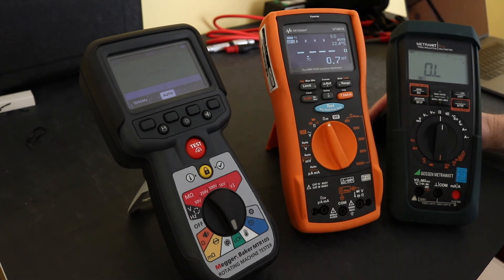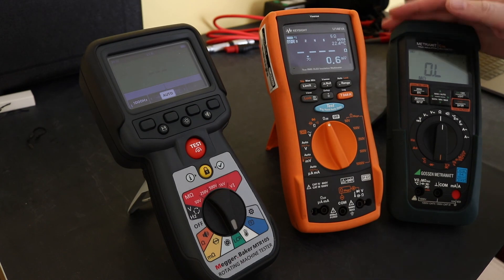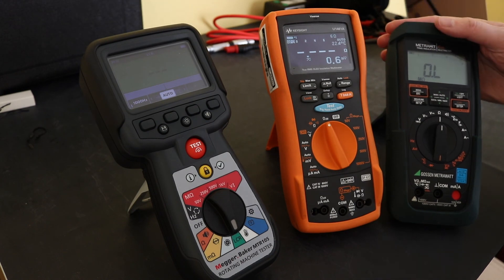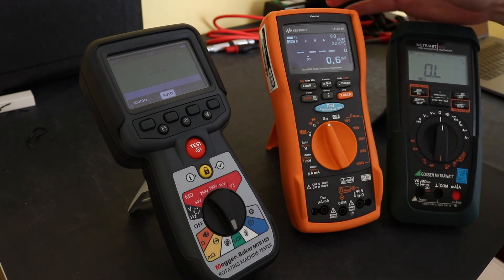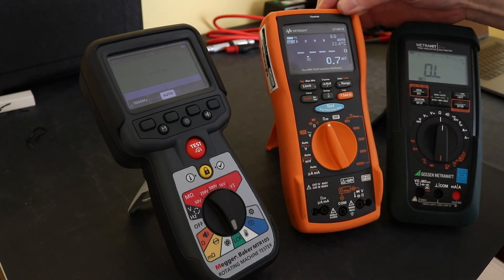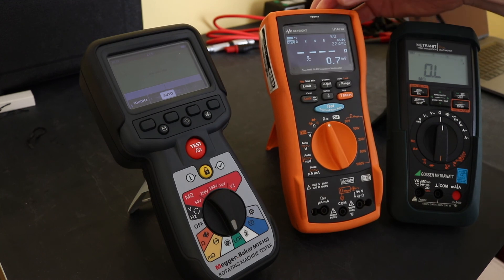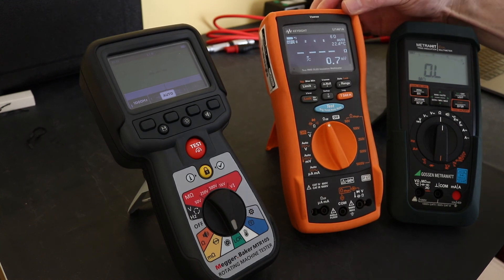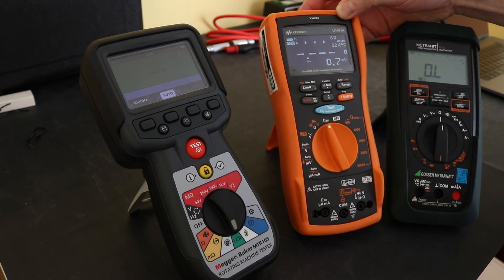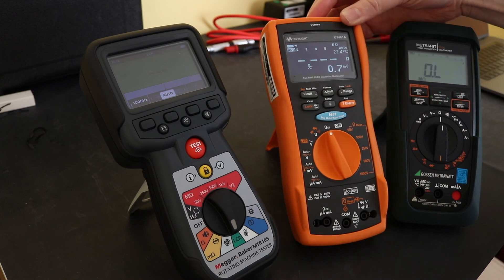It's actually then quite a close call between the Keysight and the Metrahit. If you're looking at this from the perspective of testing motors this is probably geared up a little bit more towards that. And although this does have a lot more functionality to it and it does have better accuracy, the multimeter aspect of this instrument is aimed more towards the slightly electronic side in that respect with the logging facilities that you can have with it.